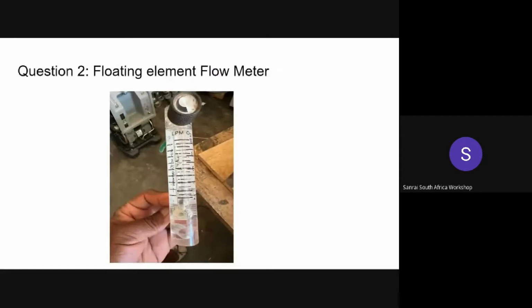Electromagnetic flow meters use magnetic coils to create a magnetic field, which changes as fluids or gases pass through a pipe. These are best used for gases and liquids that can conduct electricity. Floating element flow meters use a float encased in a pipe. The float moves up and down as fluids or liquids are forced inside the tube, generating differential pressure.